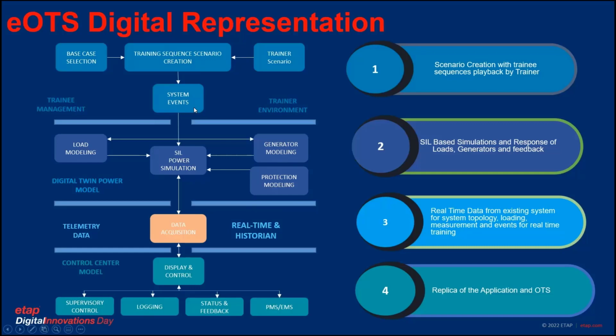It creates different scenarios and sequences required for the OTS functions, then converts the steady and dynamic simulations for the response back, converging the field elements as required—for a generator, load, or open/close breaker feedback conditions—and updates the topology and data processing and network management the way it updates in your SCADA system, so it feels like a complete true copy and replica of OTS.